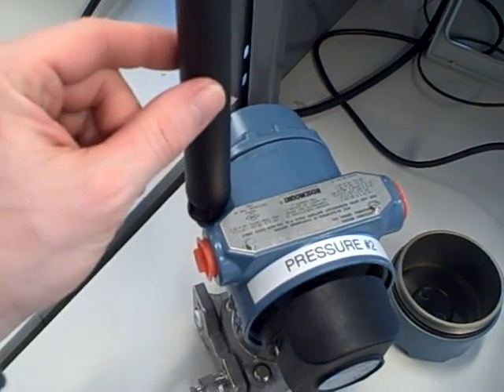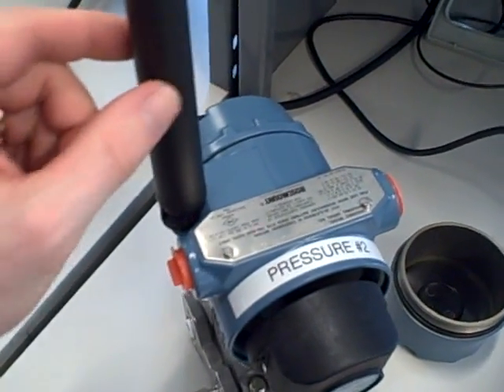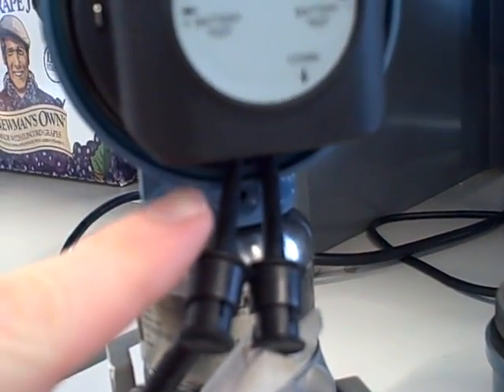This particular transmitter has an antenna on it and communicates wirelessly. However, despite the presence of an antenna, it still has terminals down here. We can clip in with a HART communicator, which we have done right here with the Model 375 HART communicator.